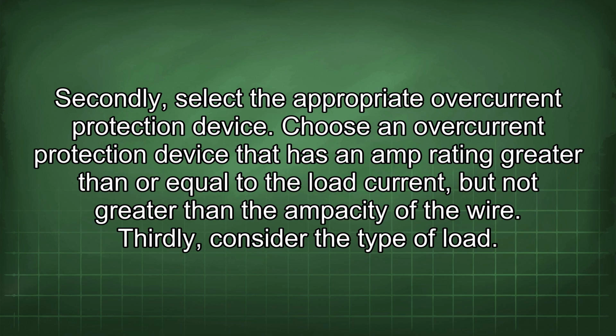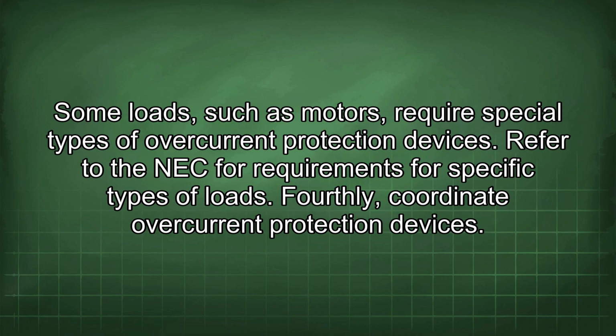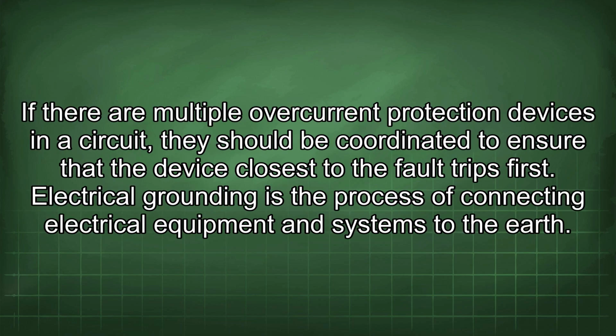Thirdly, consider the type of load. Some loads, such as motors, require special types of overcurrent protection devices. Refer to the NEC for requirements for specific types of loads. Fourthly, coordinate overcurrent protection devices. If there are multiple overcurrent protection devices in a circuit, they should be coordinated to ensure that the device closest to the fault trips first.